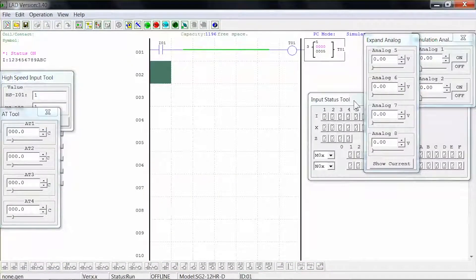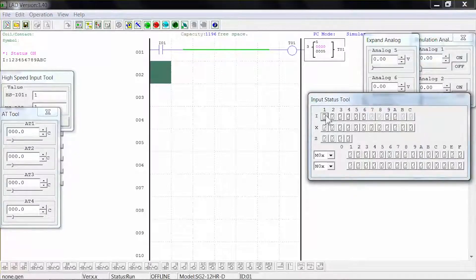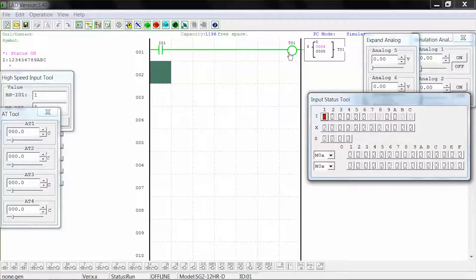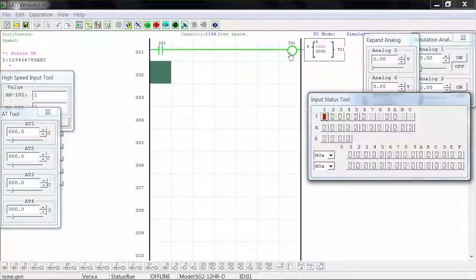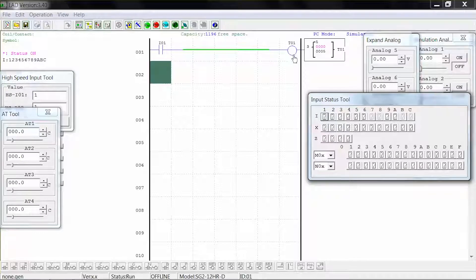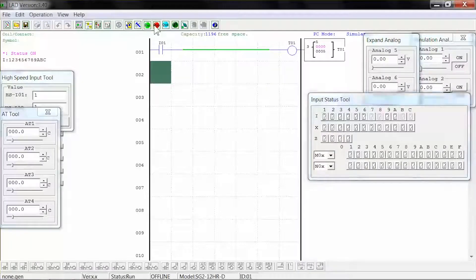In the input status tool window, close input 1. The coil activates and the timer begins to count. When it reaches 5 seconds, the coil deactivates and the timer starts again. When it reaches 5 seconds again, the coil reactivates. This flash timer pattern will continue until input 1 is deactivated, at which point the coil is deactivated and the timer is reset to 0. Press stop to stop the simulation.